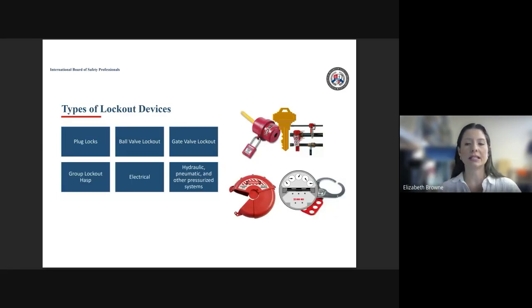We have types of lockout devices. OSHA says that we must use some type of lock, and all employees must use a lock. They say that it must be singularly identified, meaning that we all use the same square red lock, or we all use some type of lock, because they want to make sure that the lock isn't confused for something else and an employee removes it and then turns a machine on while someone's working on it. So we want to make sure it's labeled. It says who is responsible for the lockout, and then we also have tags on there to make it really obvious that this equipment has been locked out. It should not be removed, except by the employee that put it on. There should be one single key to that lock, and that key remains with the employee who put the lock on the equipment.